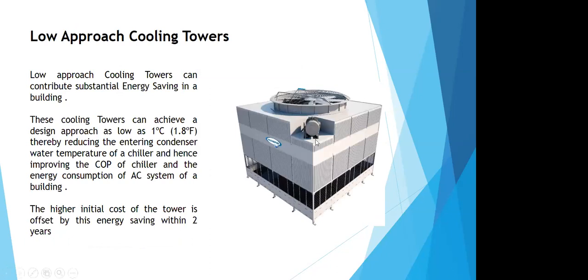So here is a low approach cooling tower. It's a counterflow design, as you can see. Low approach cooling towers can contribute to substantial energy saving. How? They can achieve a design approach of say 1 degree centigrade or 1.8 degree Fahrenheit. By doing so, they reduce the condenser water inlet temperature of the chiller, thereby improving the COP and reducing the kW per ton of the chiller. That is the way the low approach cooling tower can impact the energy consumption of the HVAC system of a building. Though the size and the initial cost of a low approach cooling tower is much higher than the standard cooling tower, which is of around 5 to 7 degree approach, the additional cost of the cooling tower can be paid back in almost less than 2 years' time.